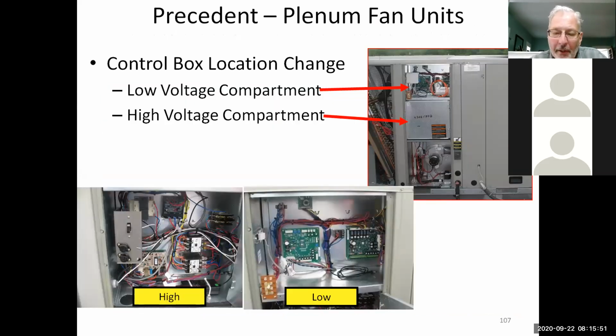So what American Standard has done is we've separated the high voltage and the low voltage, and we put a door on the high voltage side. Anytime you're working on something over 200 volts, I think, you're supposed to have hot gloves on, safety glasses, arc shield, cotton clothing, standing on a rubber pad, all that kind of stuff. So in order for us to help ensure that you guys are safe in the field, we put a door on the high voltage side, and we ask that you take great caution and use your company's safety policies when you're working on the high voltage side.